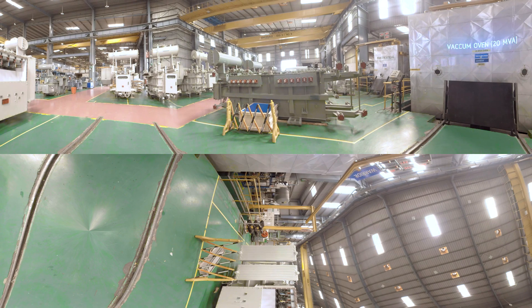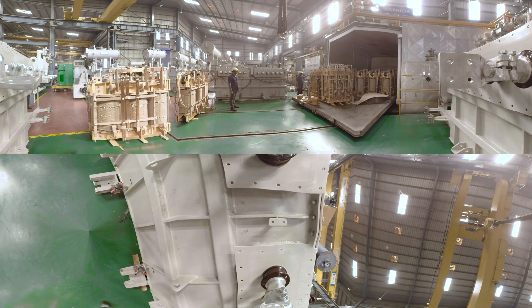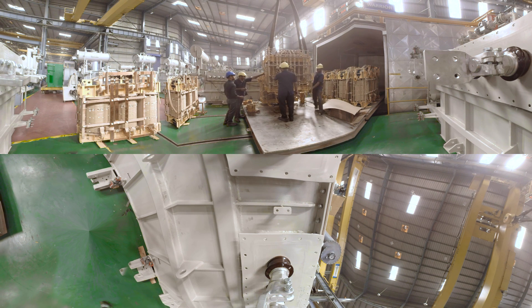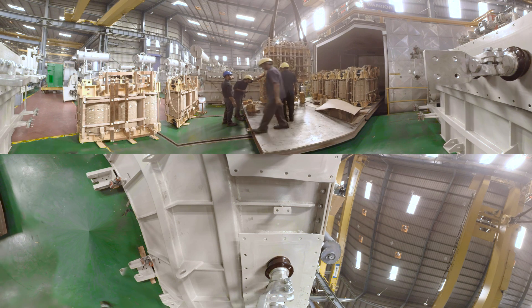After core coil assembly, the next step for an oil type transformer is heating the core coil assembly in an oven — basically a moisture removal process. For this, we have best-in-class oven technology, autoclave, and vacuum process oven. The time cycle of the ovening process depends upon the size, weight, and KVA rating of the transformer.